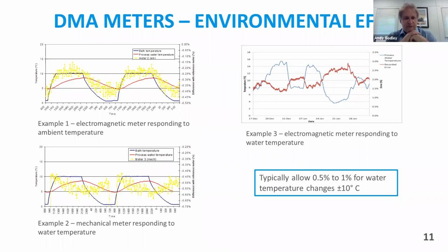Whereas if you look at the figure below, this is a mechanical meter. This was on the same test, same batch of tests. In exactly the same situation, the response of the mechanical meter follows, albeit inversely, the process water temperature, i.e. the temperature of the water that's going through the meter, not the ambient temperature. And on the top right, there's an electromagnetic meter that's doing the opposite. There's an electromagnetic meter that's responding to water temperature.